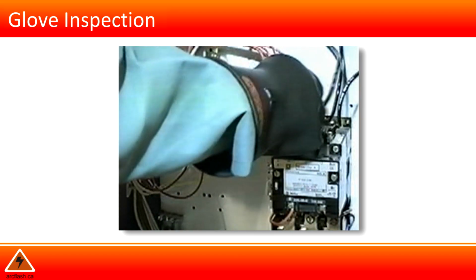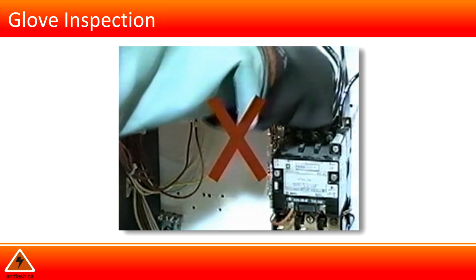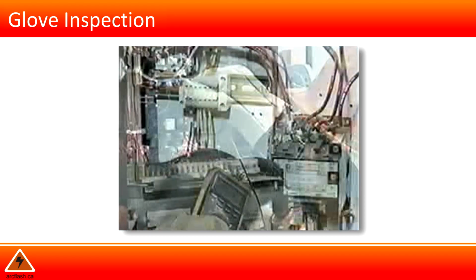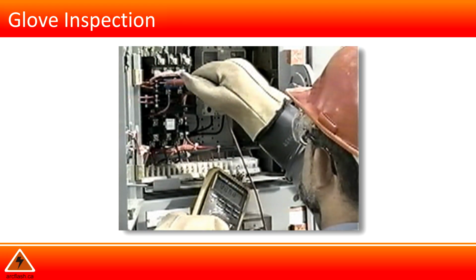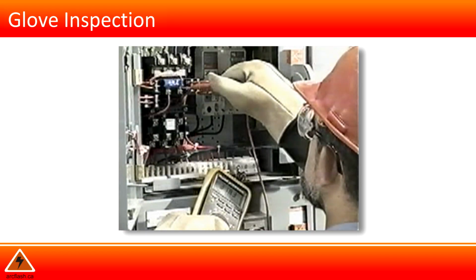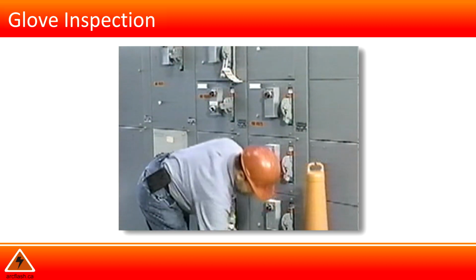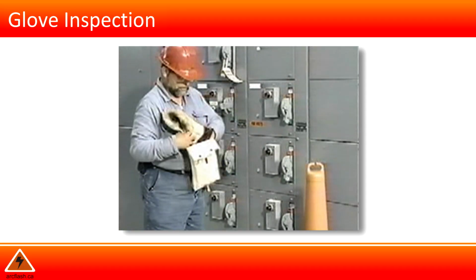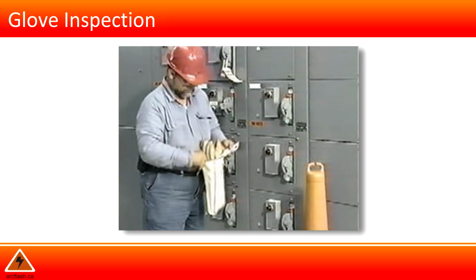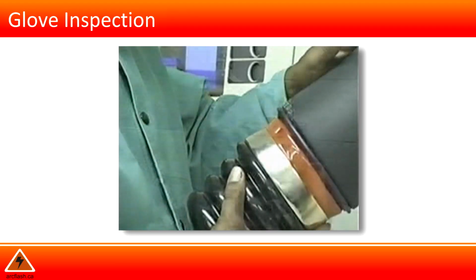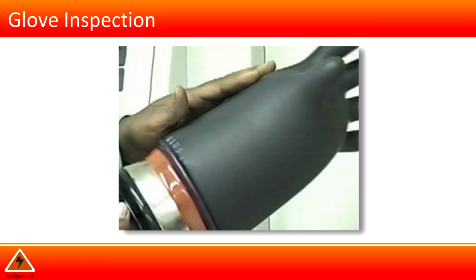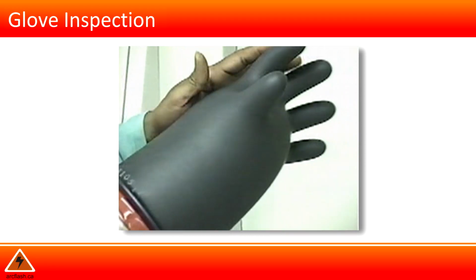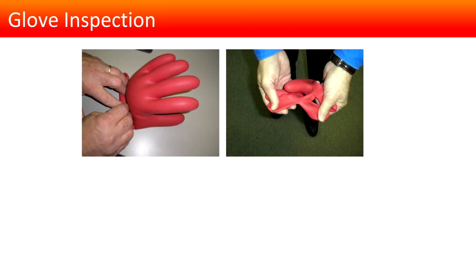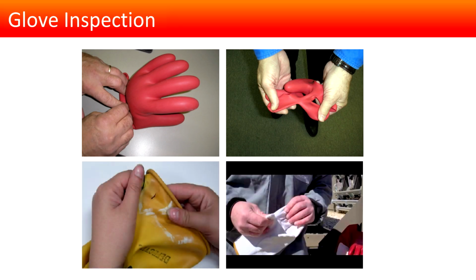Because of the importance of maintaining a glove free from holes and damage, never wear just an electrical glove by itself. Always use leather protectors over the glove to protect them from damage. This has the added benefit of offering some protection for your hands in the event of an arc flash. When not in use, your electrical insulated gloves should be stored in an approved storage device. Electric gloves that will be reused must be tested and recertified by an approved testing laboratory every 6 months. But don't forget to perform your own air test prior to each day's use. In the video, we saw the use of a glove inflator. However, other means may be used, such as shown here, for glove inspection.